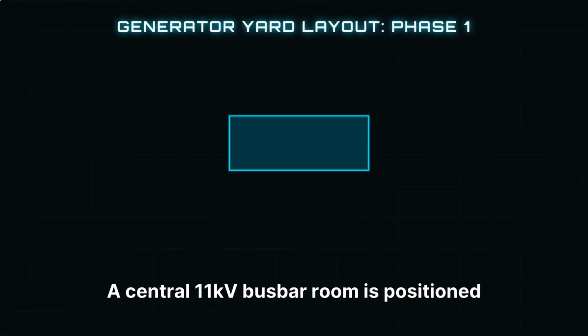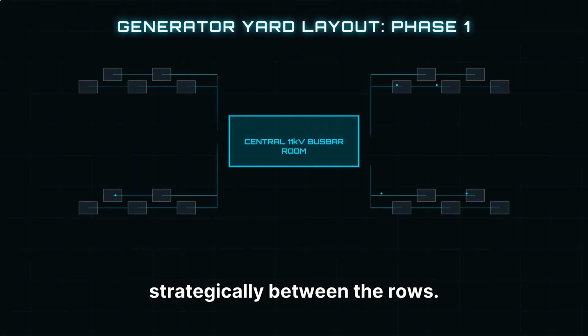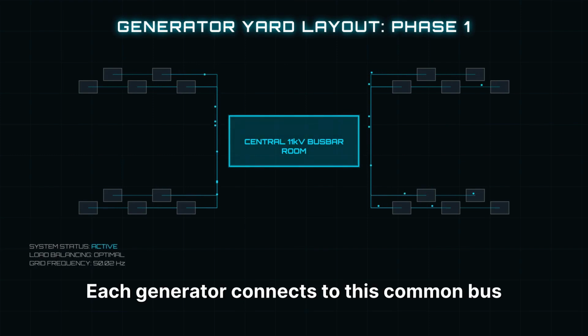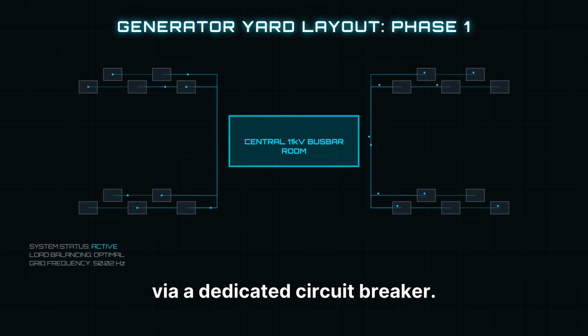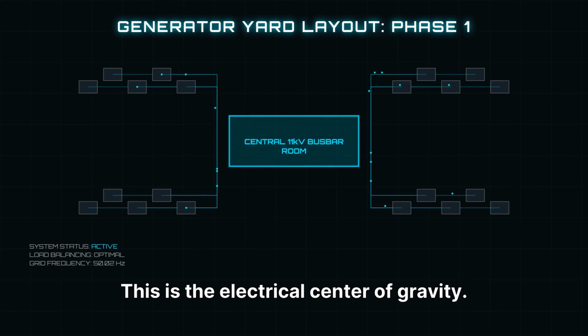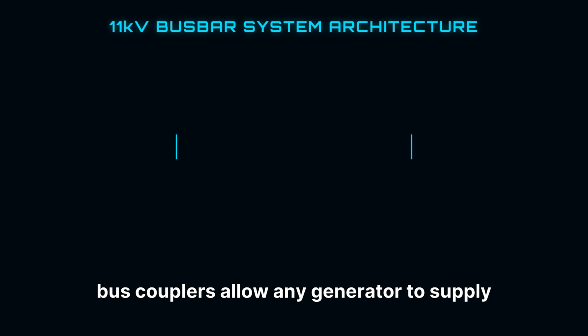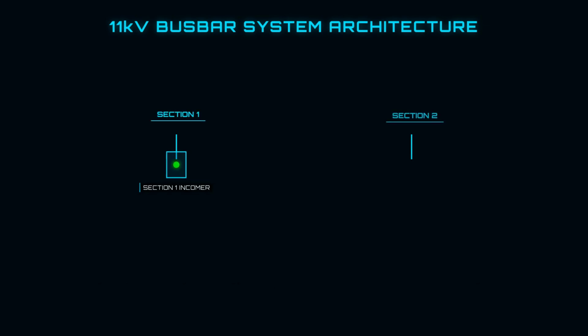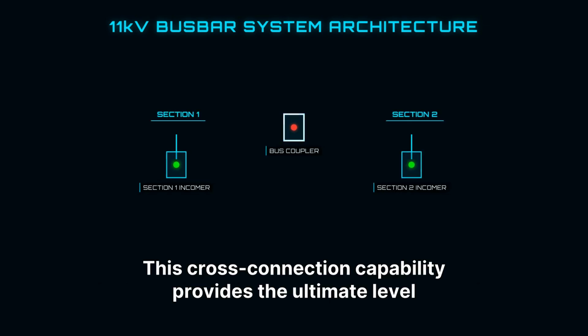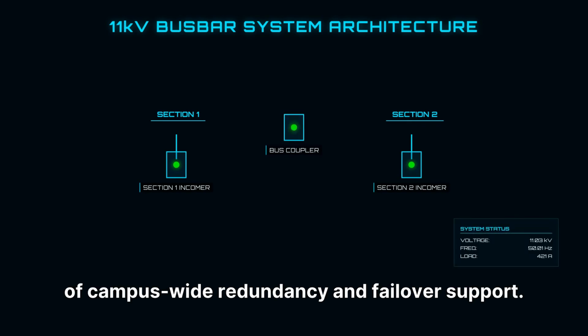A central 11 kV busbar room is positioned strategically between the rows. Each generator connects to this common bus via a dedicated circuit breaker. This is the electrical center of gravity. The bus is sectionalized per hall, but bus couplers allow any generator to supply any hall. This cross-connection capability provides the ultimate level of campus-wide redundancy and failover support.